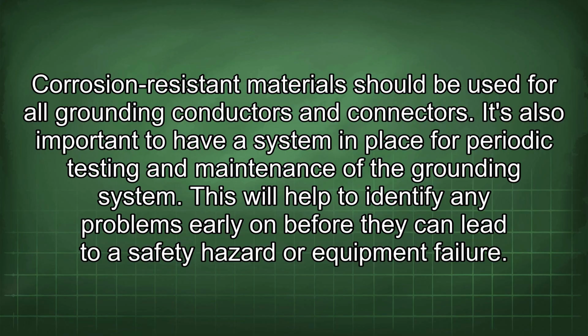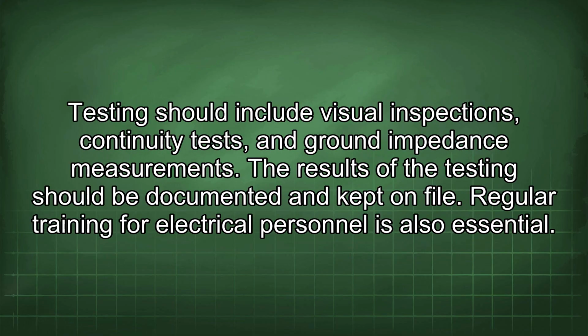It's also important to have a system in place for periodic testing and maintenance of the grounding system. This will help to identify any problems early on before they can lead to a safety hazard or equipment failure. Testing should include visual inspections, continuity tests, and ground impedance measurements. The results of the testing should be documented and kept on file.